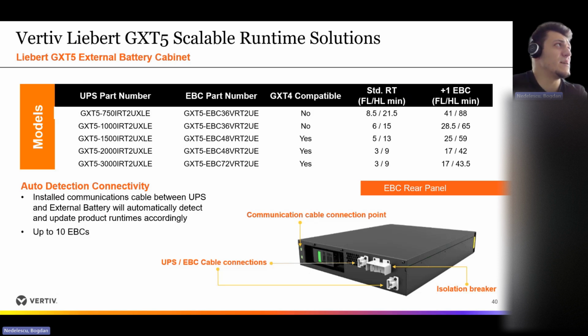So let's take an example. If we take the 2 kVA version of the GXT5, we can see that the default operation time of the unit at 100% load is 3 minutes. But if we also purchase an external battery cabinet and connect it to the UPS, the runtime of the unit will be around 17 minutes at 100% load. And if we go with an additional external battery cabinet, so this time we'll have two, we will have around 27 minutes at 100% load. So I think you get the idea. We can ensure a very good runtime for this UPS because, as I said, it can support up to 10 external battery cabinets.